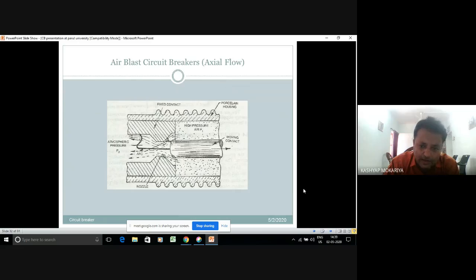This is the axial flow breaker. As compared to radial flow, I will just show you the direction of the air here, how that air is blown, because the rate of the dielectric strength will build up, and obviously your arc will get extinguished.